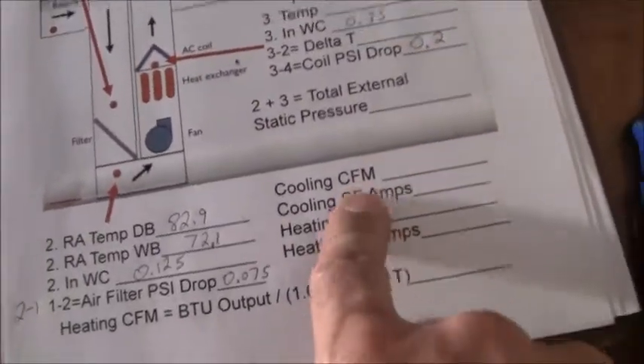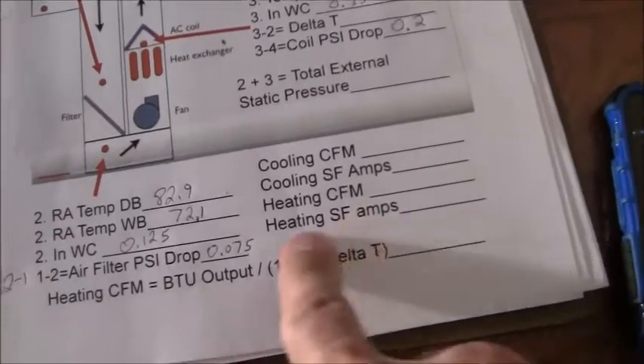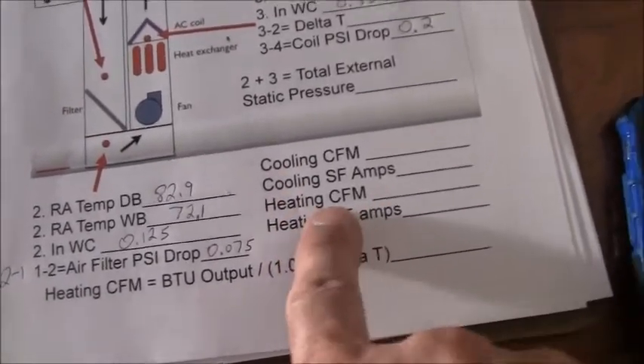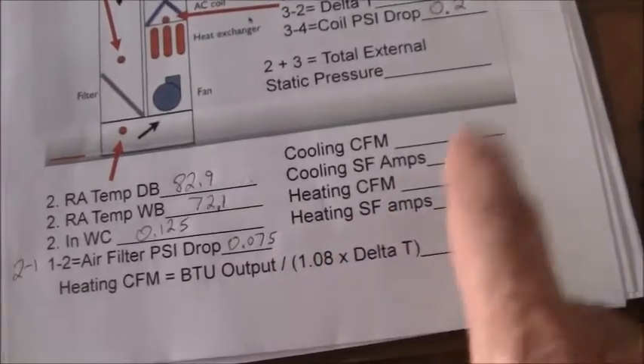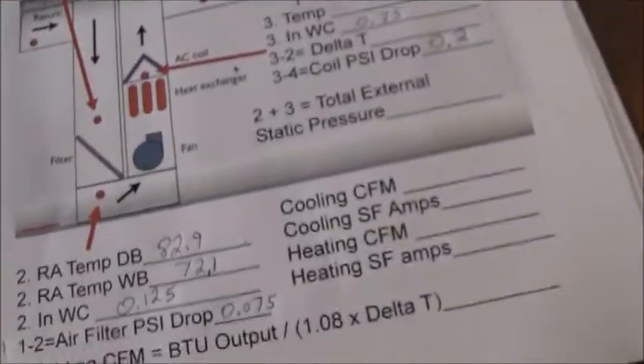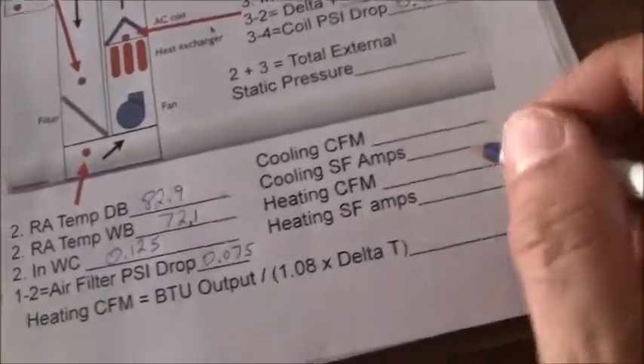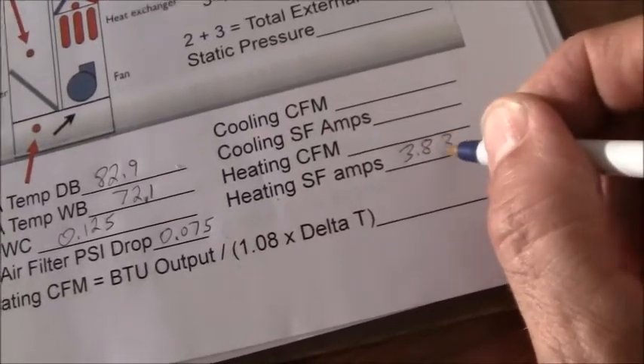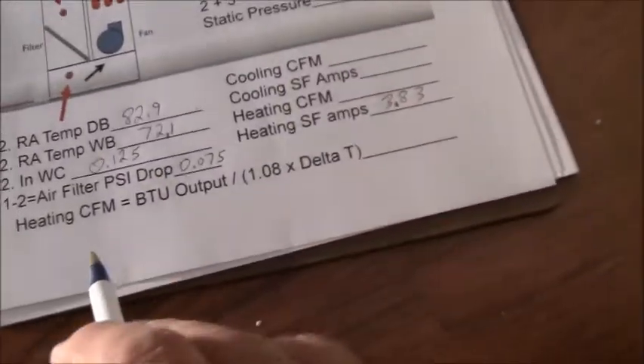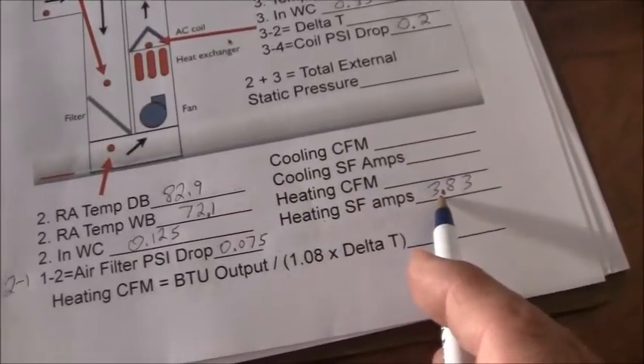Now, we want to know what the amps are. Right now we're in heating mode. Let's go with supply fan amps. Let's figure out what that is right there. So my meter shut off, but let's put it back on. Go amperage AC. There's my backlight right there. And right now the fan is drawing 3.83 amps. Okay, it's 3.83. So let's write that down. And that goes heating supply fan amps 3.83.